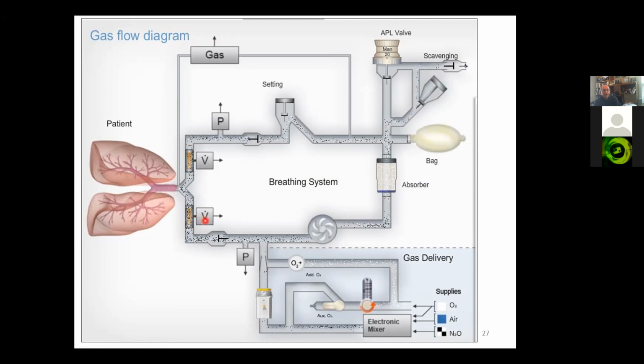A flow meter, V dot, so first time derivative of volume, flow, goes to the alarm and display computers. This valve permits gas to go to the patient, but not back when the patient exhales, when pressure here is greater than the controlling computer is permitting gas pressure to be here. So all of the control structure of the ventilator is essentially connected in here. This is where volume settings and pressure settings and gas concentration settings are coming from. This is the gas delivery equipment. The patient's exhale gas goes out here to this valve. Pressure and flow rate are reported to the computer here.